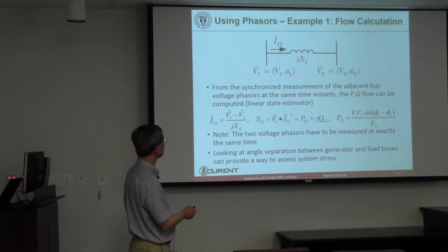So what can you use the phasors for on the surface? You can do flow calculations. If you measure the voltage phasor here and the voltage phasor on the next bus over — remember, voltage is not just magnitude, it's also phase — you can easily calculate the flow between the two. All you have to do is V1 minus V2 over the reactance.